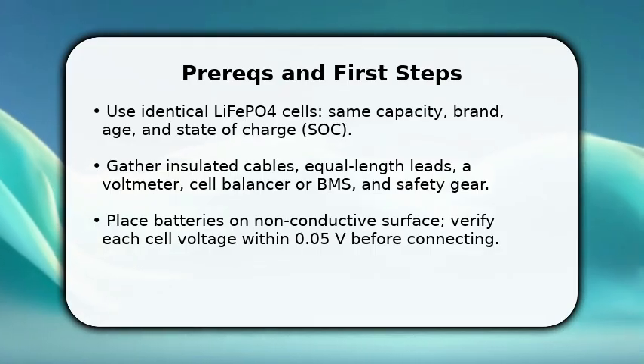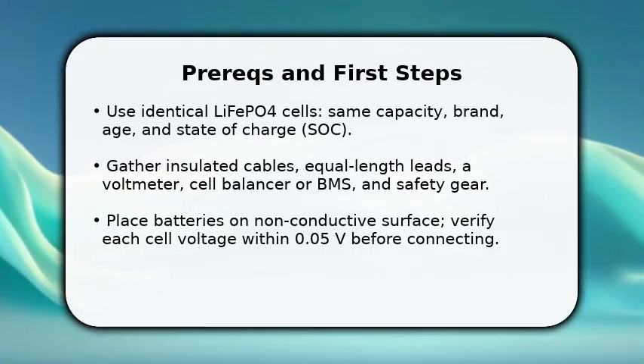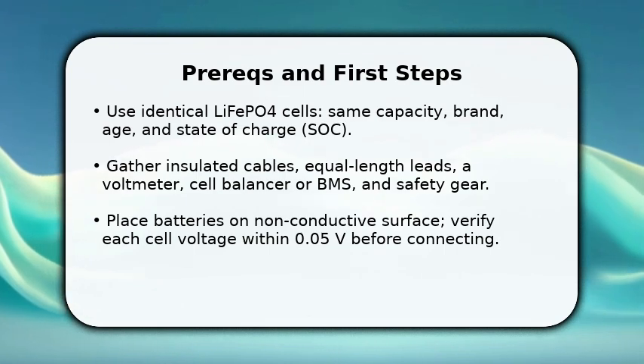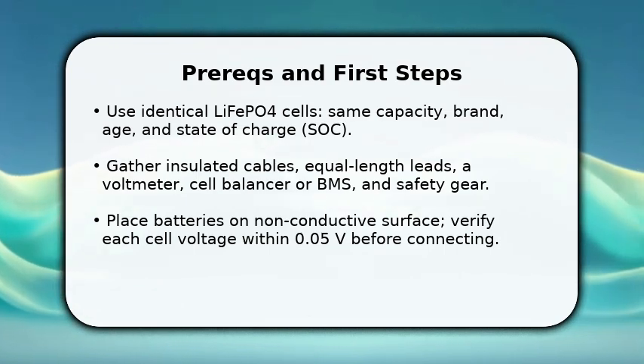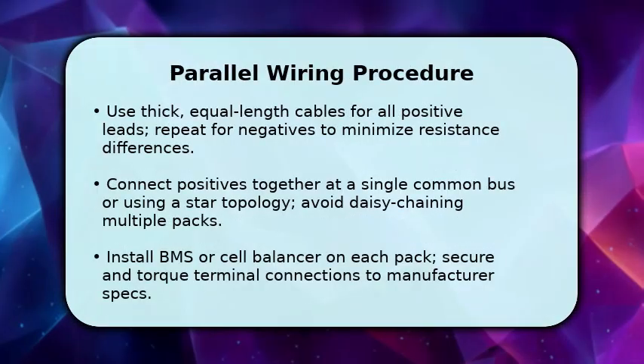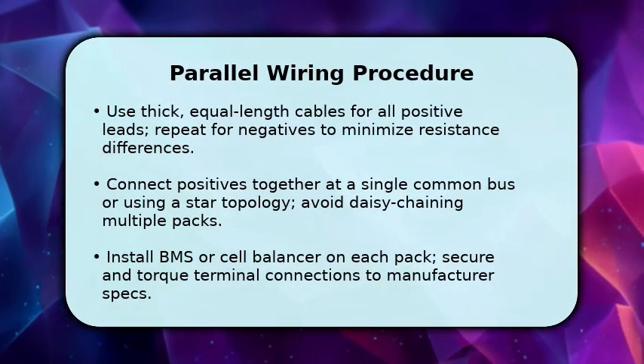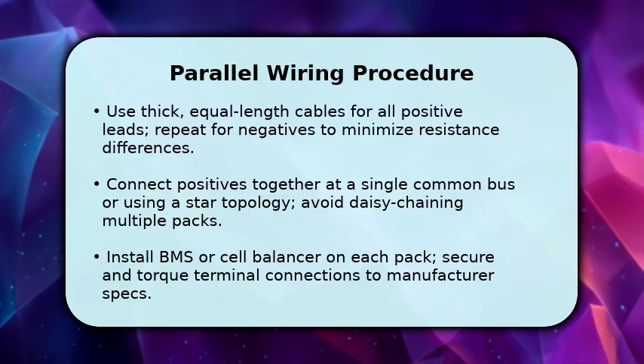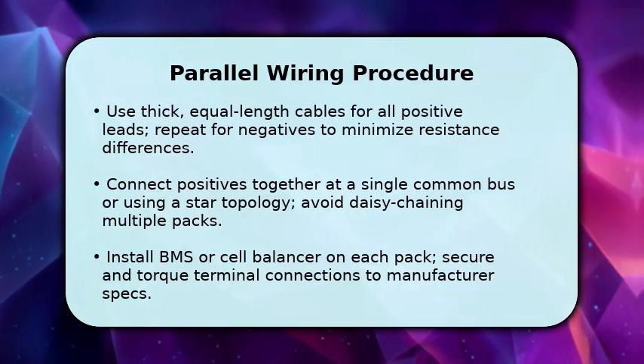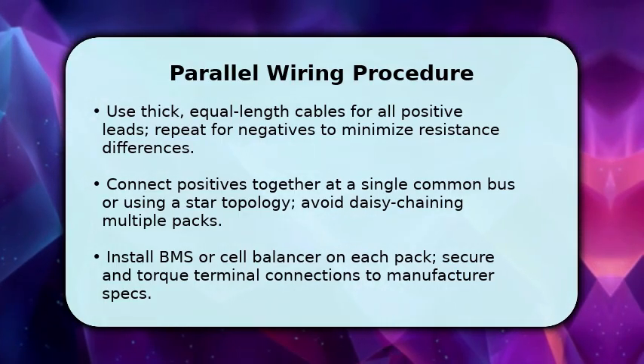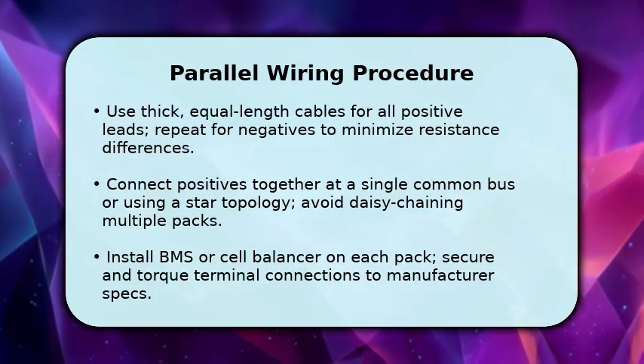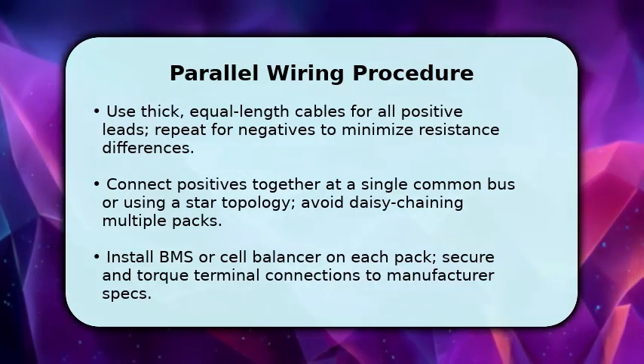Once done, position your main positive cable for the next step and keep the system open-circuited until all parallels are ready. You now wire in parallel using a star or common bus method so each battery sees the same path to the load. First, attach equal-length positive cables from each battery to the positive bus, then do the same for negatives to the negative bus.